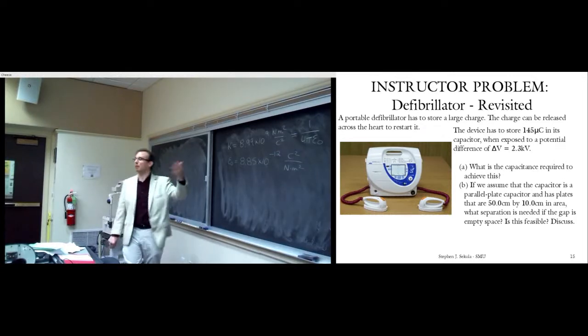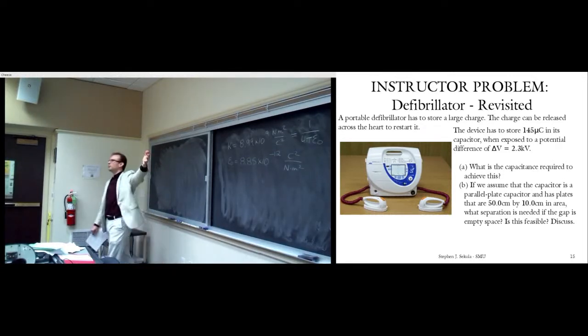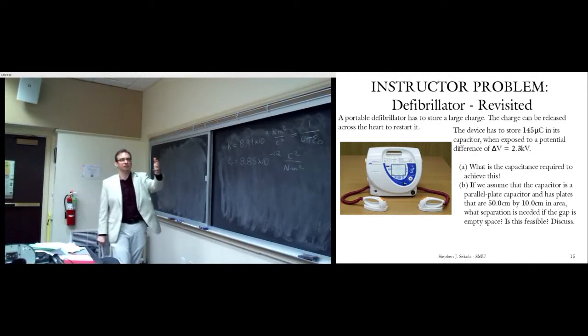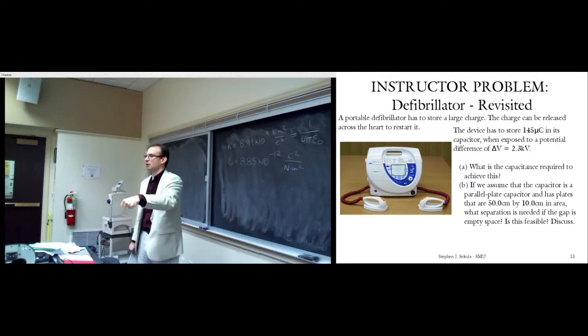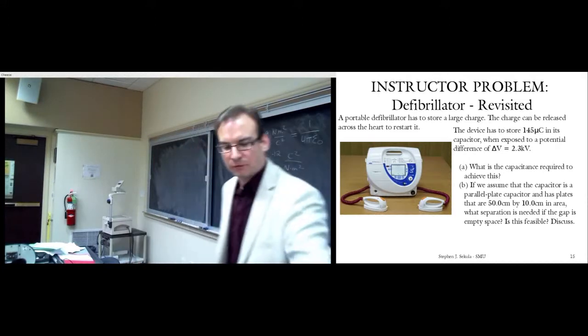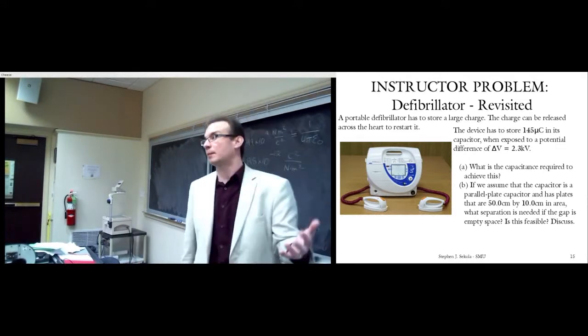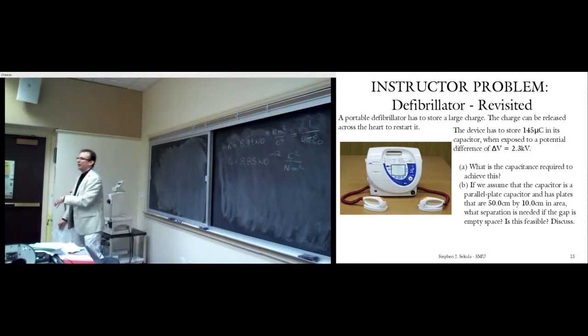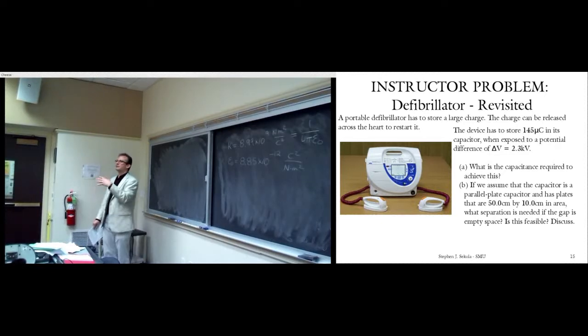Now, there's no doubt a battery in this, because even if you put a big capacitor in this, they leak. So you don't want to let this thing just sit with a capacitor with a stored charge in it all day. It won't have as much charge in an hour. And you don't want that to be the difference between saving a life and letting a person die. So you've got a battery, but you've also got a capacitor. And the beautiful thing about a capacitor is it can deliver its energy very quickly, nearly all at once. Getting a battery to do that is very difficult. You could blow the battery up if you do that.